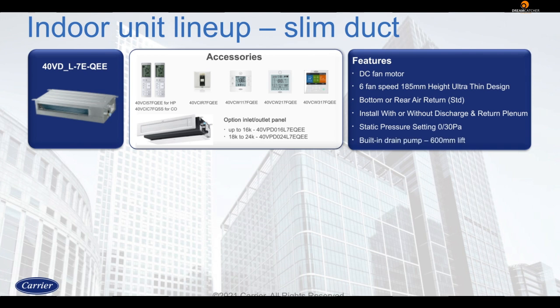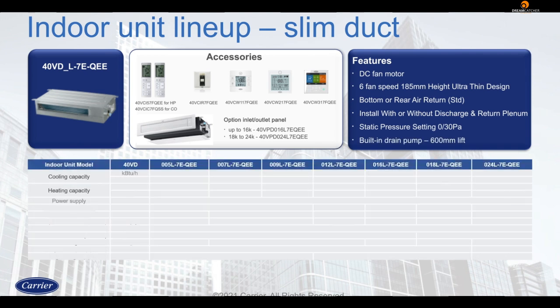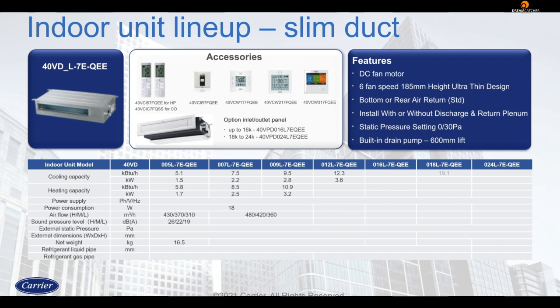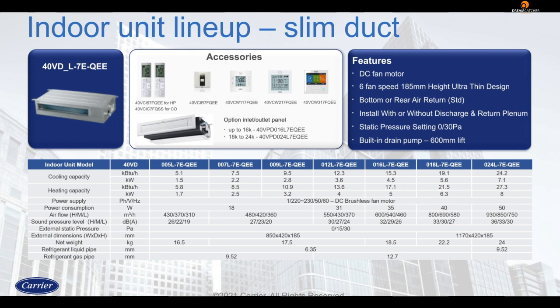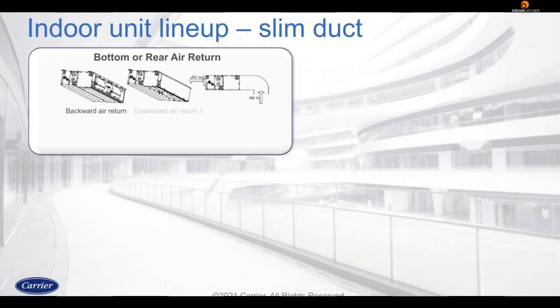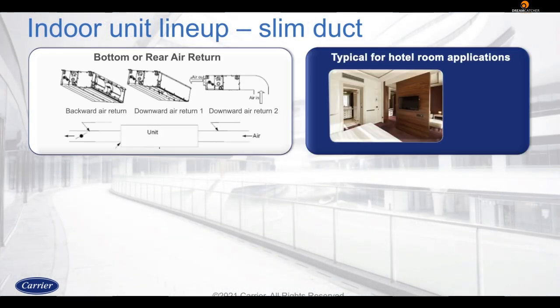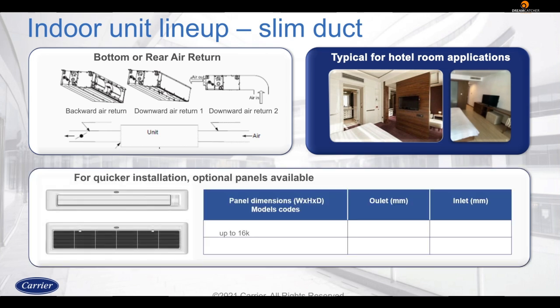600 mm lift. Bear in mind that all ducted indoor units do not come with a wireless receiver for the wireless controller. If a wireless controller is required, the receiver has to be ordered separately. Wireless controllers come in 2 different models for cooling only or heat pump systems. Cooling only systems don't come with a heating button. The slim duct is ideal for hotel room installations and comes with optional panels for quicker installation.